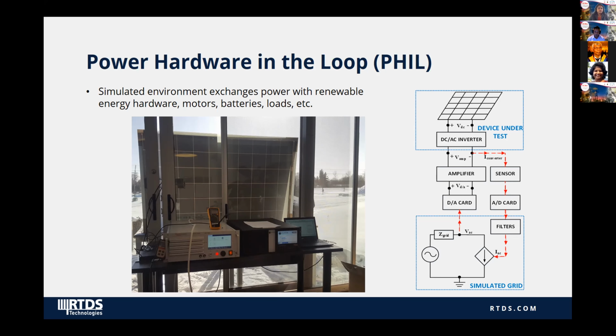You can provide different types of firing pulses out from the simulator to control external power electronic devices, or alternatively simulate your power electronic devices inside the simulator and use real controllers, which provide firing pulses back to the simulator to control the simulated circuit. Depending on your requirement, you can simulate either power electronic controllers or power electronic devices inside the simulator. Certain utilities use replica controls, especially for HVDC controls with the RTDS simulator, having both a real controller and a replica model in RTDS, so they can sometimes control even a real HVDC controller unit using the control model simulated inside the simulator.